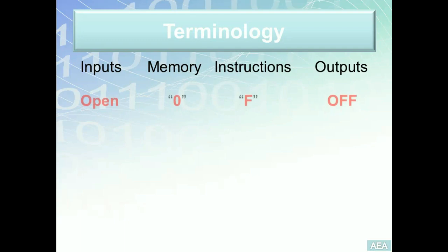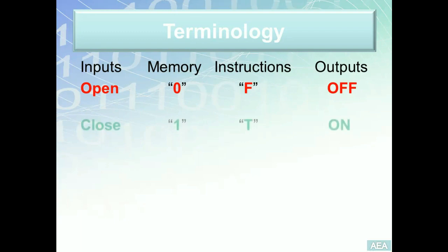Before we introduce the first discrete instruction, it's really important to understand how the PLC internal memory is going to interpret and read the states of discrete inputs and outputs. Discrete inputs and outputs can be one of two states — hence the name discrete. A discrete input could be in an open state or a closed state. We don't care what type of switch it is — push button, level switch, or toggle switch. What matters is: if that switch is currently open, it will be read in the PLC memory as logic zero; if it is in the closed state, it will be read as logic one.